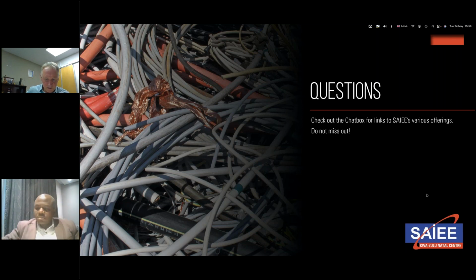Thank you, Shepard, and the attendees for those questions. Yes, the soil thermal resistivity is not affected by the addition of this particular stabilizing agent. The addition is between 1 and 2% by volume, and it can go up to about 5%. The tests done by the soil laboratory, which was engaged by the supplier, have shown that the thermal resistivity is not affected at those levels. Remember, this is not a product that's supplied by Aberdare.